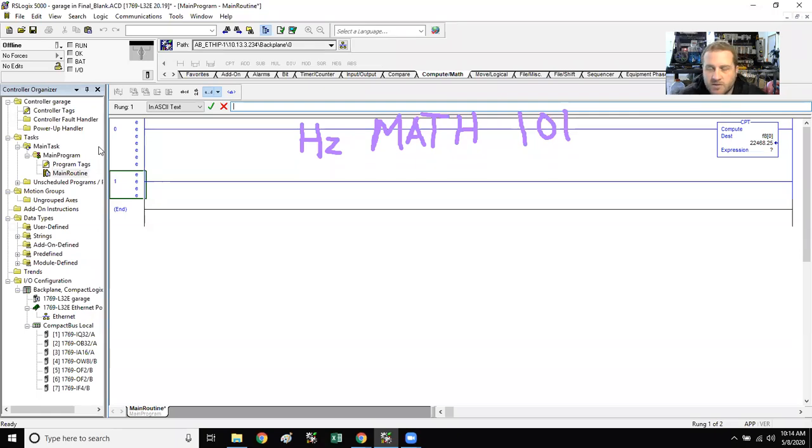So those are two numbers that you're going to need to know. We're on to something. 6241, 31206. Okay, so we're trying to go from 0 to 60 hertz on a 4 to 20 milliamp signal from 6,241 to 31,206. Yep. Okay.